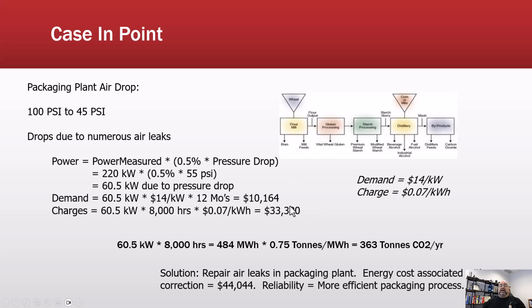Well, let's take a look at the tie. Now, in the very next presentation we do next week, we're going to talk about where you can get these numbers and how to apply them. So let's say 60.5 kilowatts times 8,000 hours. We'll convert that to megawatt hours by dividing by 1,000. That's 484 megawatt hours. In 1999, in Illinois, where this was tested, we were at 0.75 tons per megawatt hour emissions. That comes out to 363 tons CO2 per year. That means that in addition to reducing my cost of operation, I also start addressing the reduction in CO2 emissions.